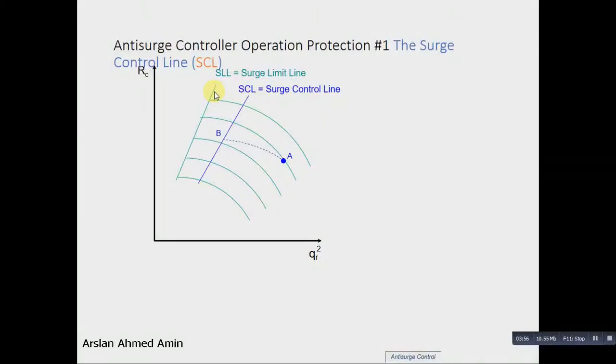Defined for the compressor map, we normally use a 10% margin between the surge limit line, which is the actual point of surge, and the surge control line. Normally there is a 10% margin.